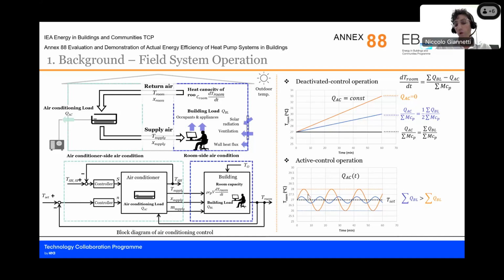The orange line is maybe somewhat different, a case that might be representative of lower load, where the control in some conditions is not able to adjust the compressor speed or control parameter to meet exactly or to move around the set point. And at a certain point, we'll have to switch off the compressor. And so we will have a system that might operate in a cycling on-off operation.